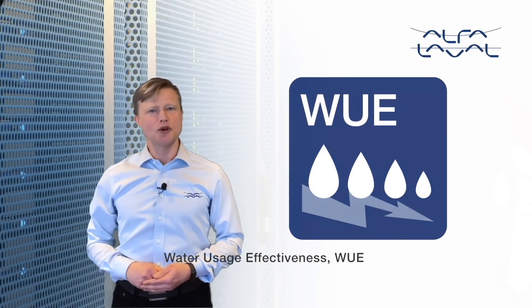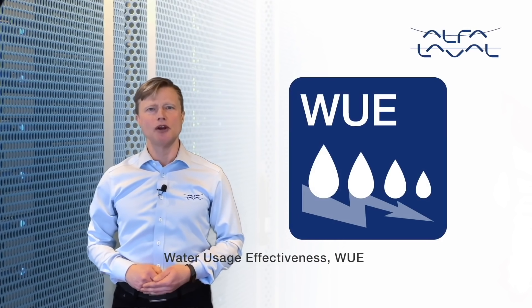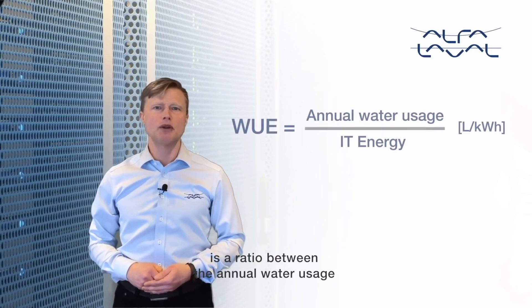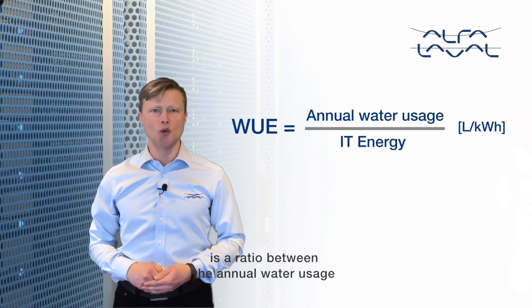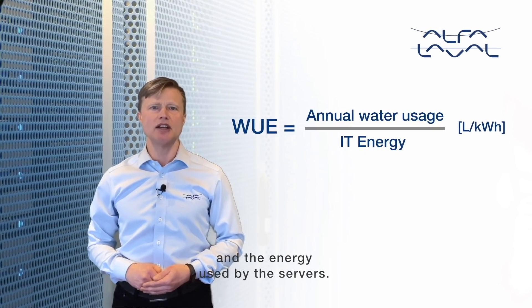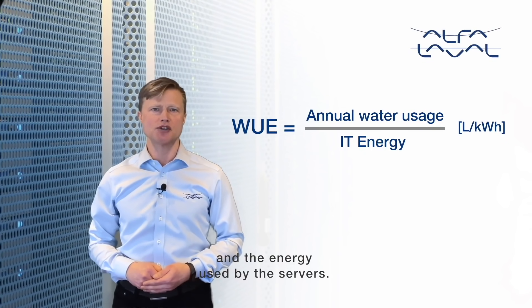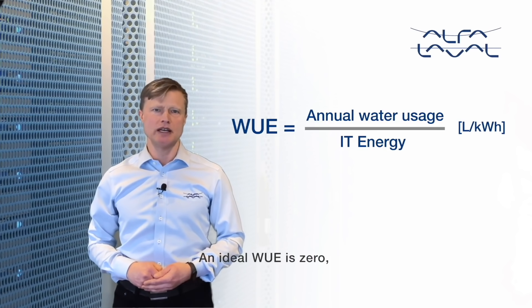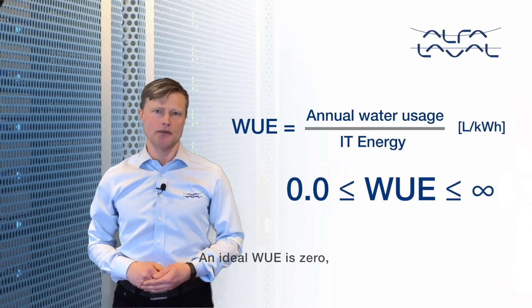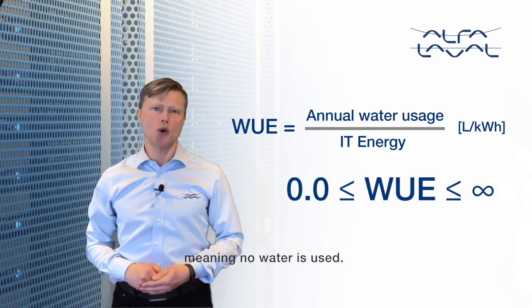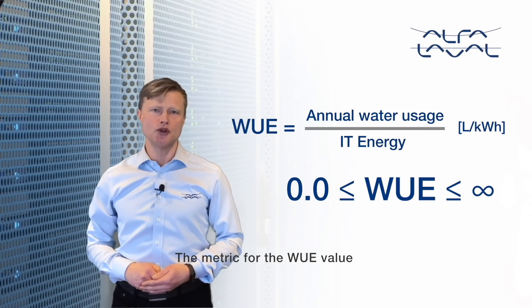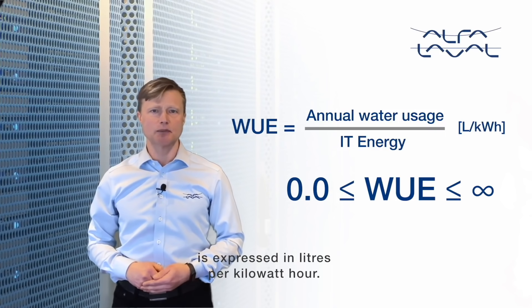Water Usage Effectiveness (WUE) is a ratio between the annual water usage and the energy used by the servers. An ideal WUE is zero, meaning no water is used. The metric for the WUE value is expressed in liters per kilowatt hour.